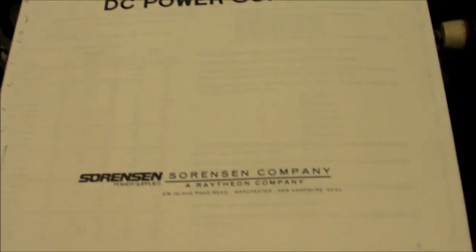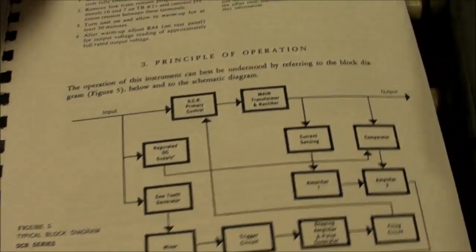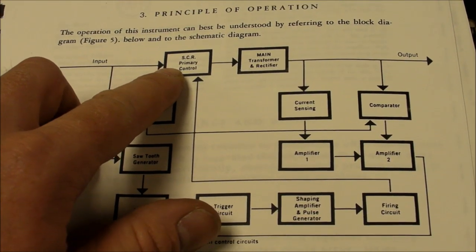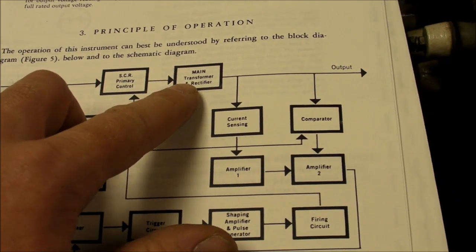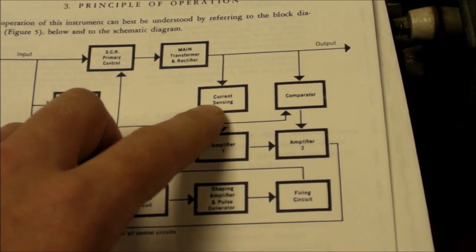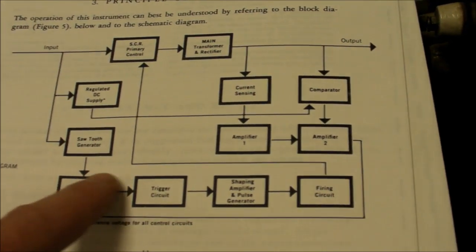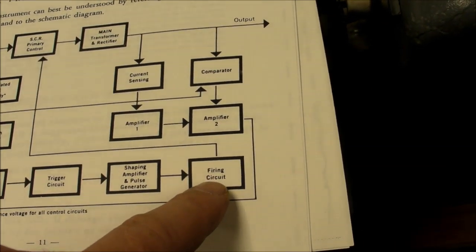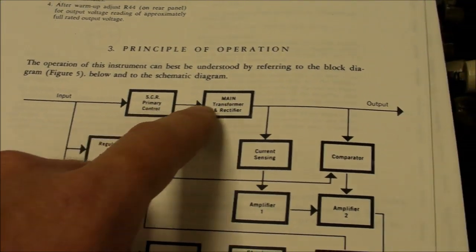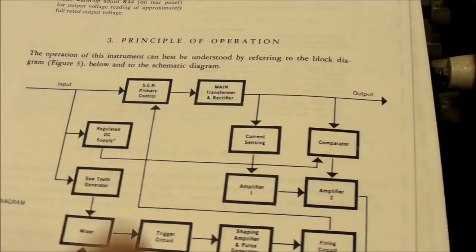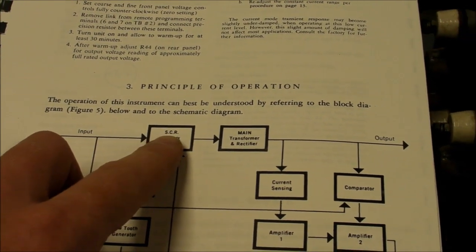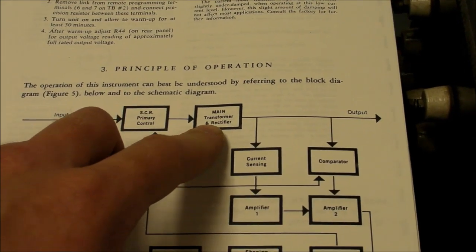And, well, I do have a copy of the manual right here. And it looks like I was right. Here's the input. Goes to SCR primary control, and then to the main transformer and rectifier. Then there's current sensing through that current shunt resistor, and then some amplifiers and a whole bunch of other stuff, ultimately ending at firing circuit. And then that goes back up to SCR control. So that's how it's able to maintain certain voltages and currents on the output, simply by controlling how much of the line voltage actually makes it into the main transformer.